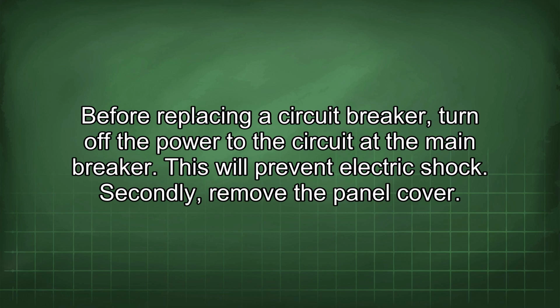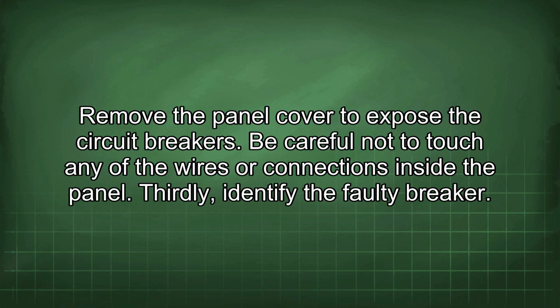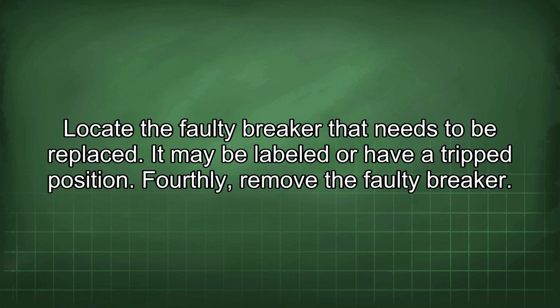Secondly, remove the panel cover. Remove the panel cover to expose the circuit breakers. Be careful not to touch any of the wires or connections inside the panel. Thirdly, identify the faulty breaker. Locate the faulty breaker that needs to be replaced. It may be labeled or have a tripped position.